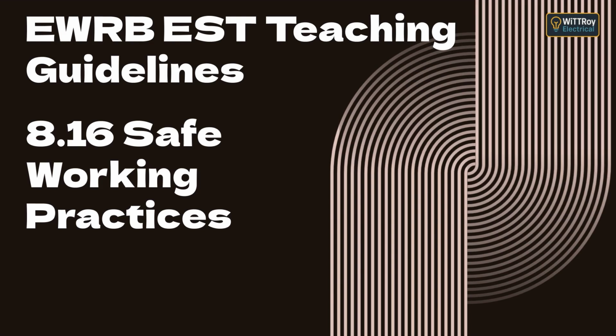Test instruments must comply with Cat 3 or Cat 4 safety ratings depending on the circuit location. Before use, check the leads and probes for damage and confirm calibration is current. Damaged tools or meters can be as dangerous as live wires. Topic G, Dead testing versus live testing.